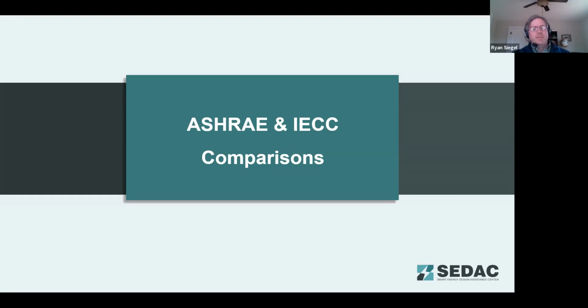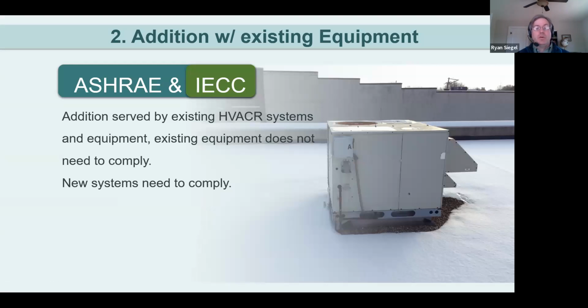Well, thank you. So these are going to be provisions that are found in both and may have similar or even identical requirements. Here, understand that when you have an addition onto an existing building, but you're going to serve it from existing equipment, ASHRAE and IECC do allow basically grandfathering that equipment in. So if you are extending HVAC equipment and ductwork to serve an addition, you don't have to upgrade those systems in order to comply. But if you are putting in a new system, then it does need to comply with the new requirements.